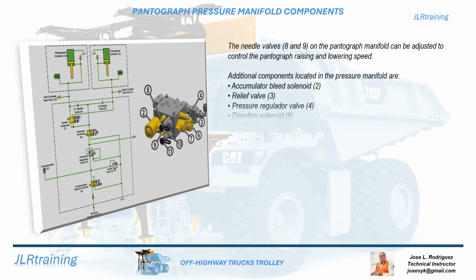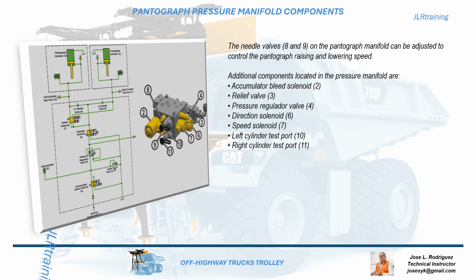Pantograph pressure manifold components. The needle valves, 8 and 9, on the pantograph manifold can be adjusted to control the pantograph raising and lowering speed. Additional components located in the pressure manifold are accumulator bleed solenoid, 2, relief valve, 3, pressure regulator valve, 4, direction solenoid, 6, speed solenoid, 7, left cylinder test port, 10, right cylinder test port, 11.